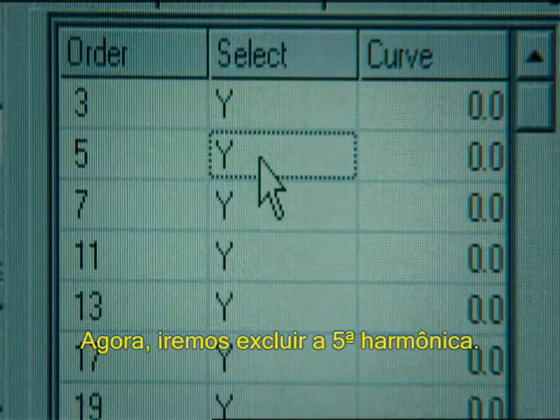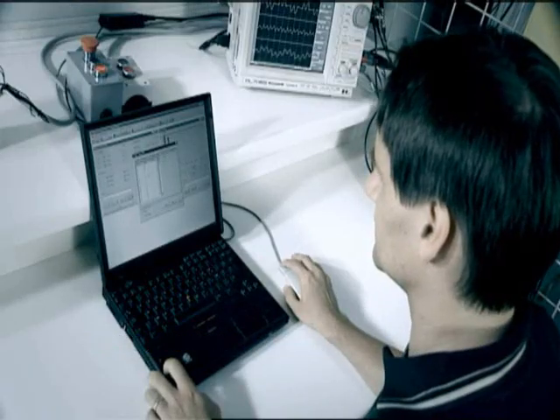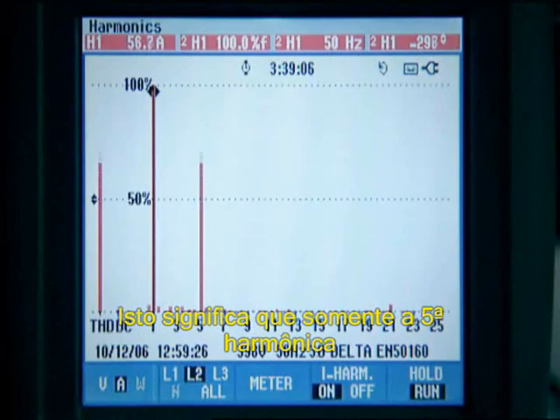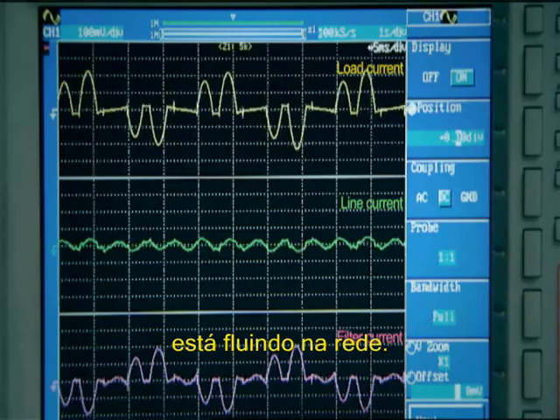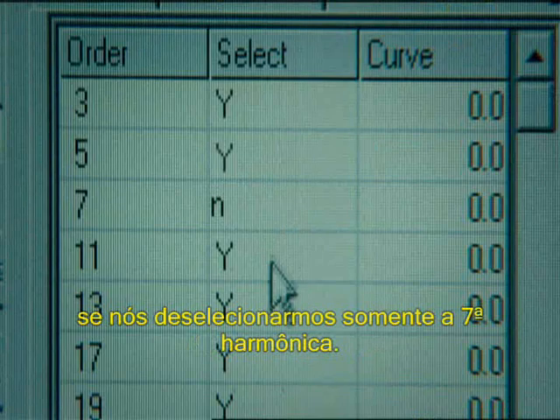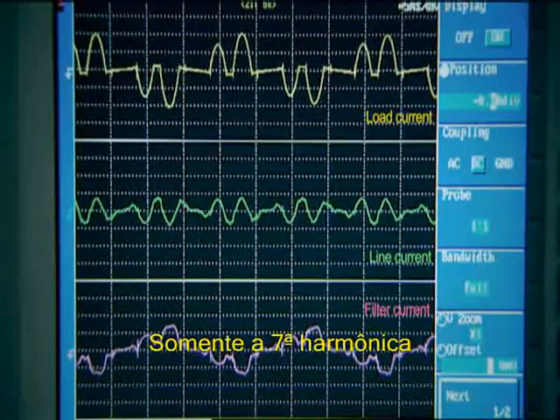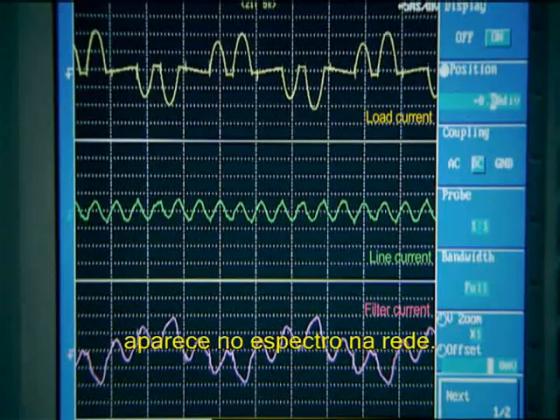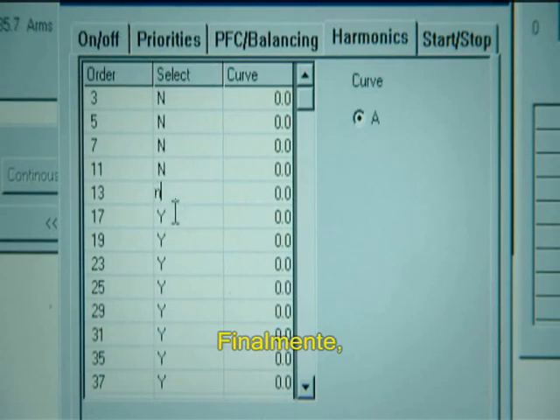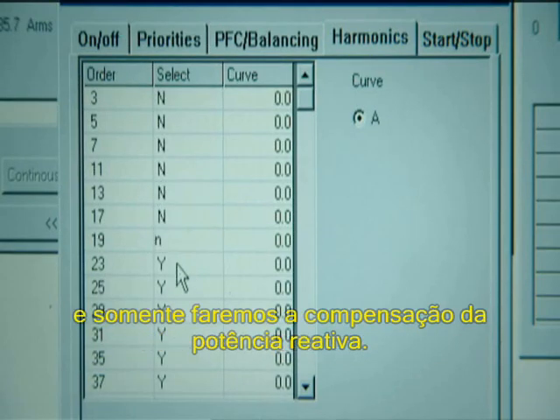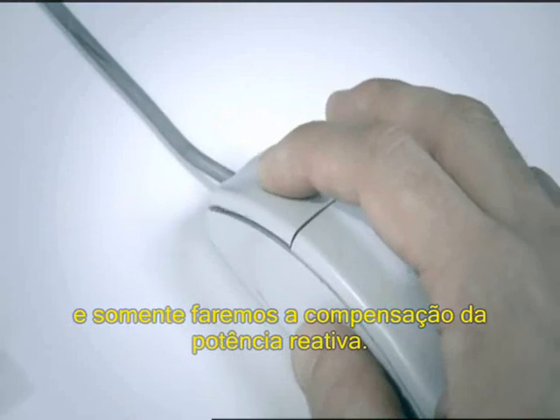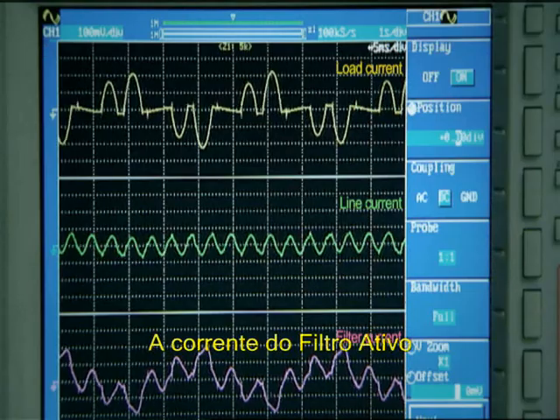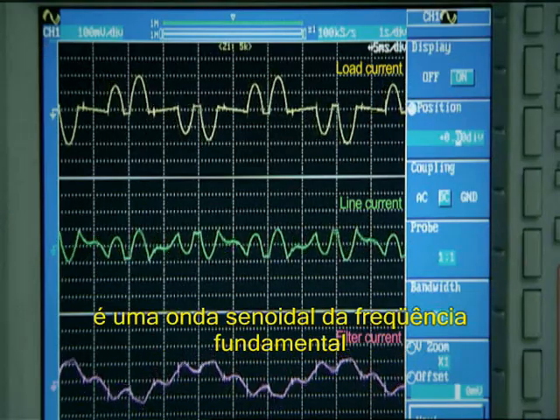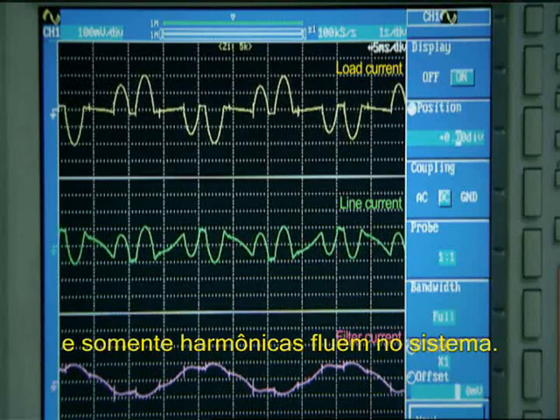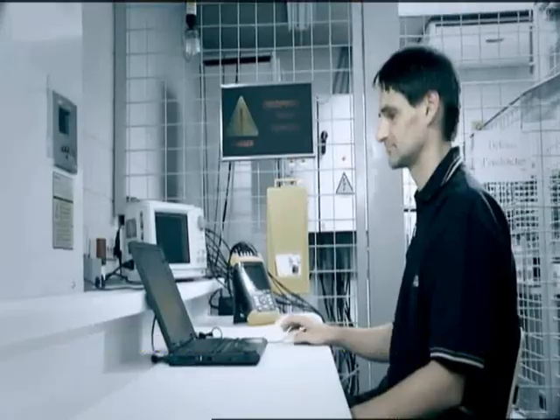We will now deselect the 5th harmonic. This means that only the 5th harmonic is flowing in the line. The same happens if we only deselect the 7th harmonic. Only the 7th harmonic appears on the spectrum and in the line. Finally, we'll stop filtering and only perform reactive power compensation. The active filter current is a sine wave with the fundamental frequency and only harmonics flow in the system.